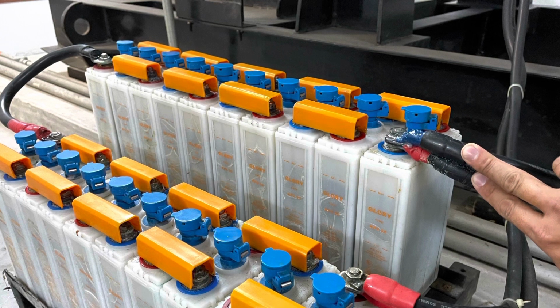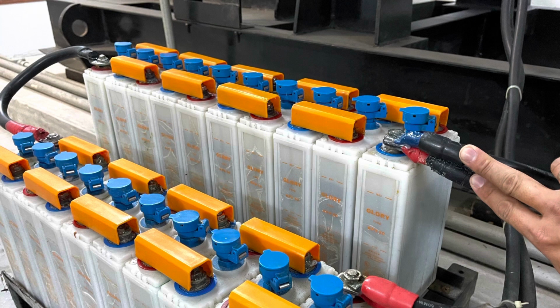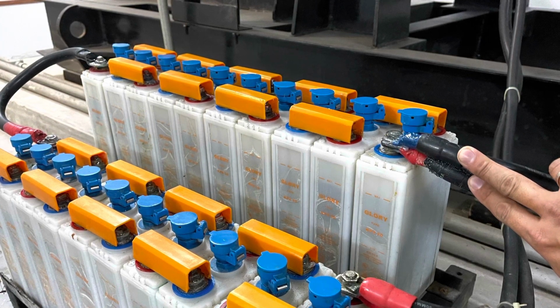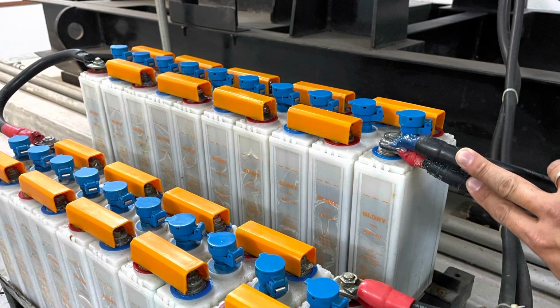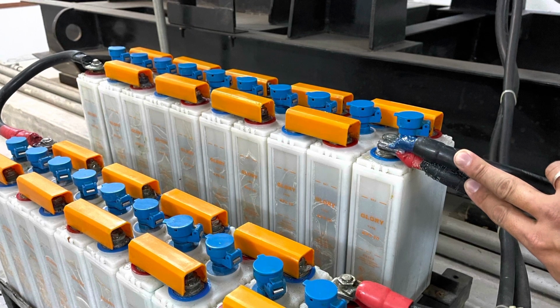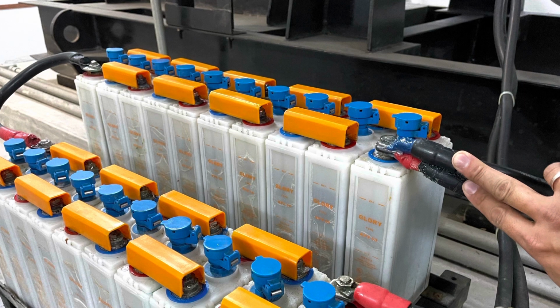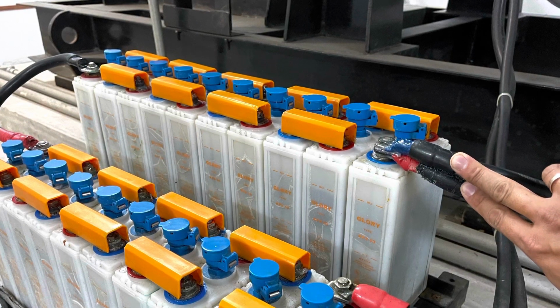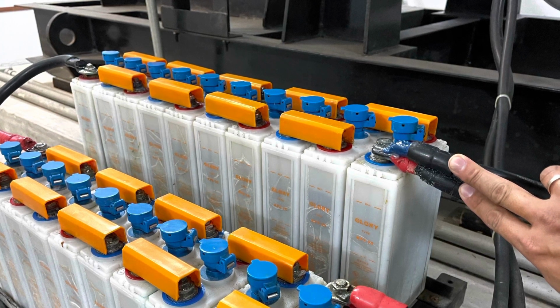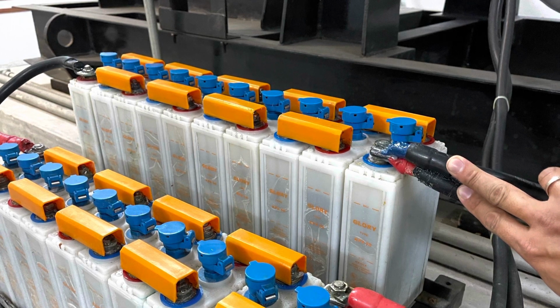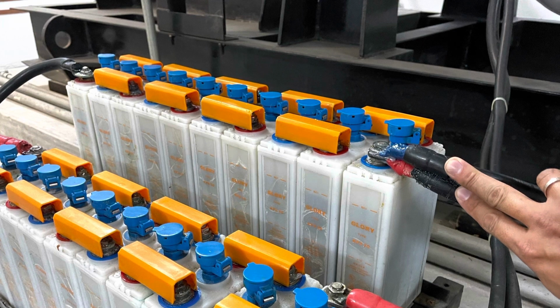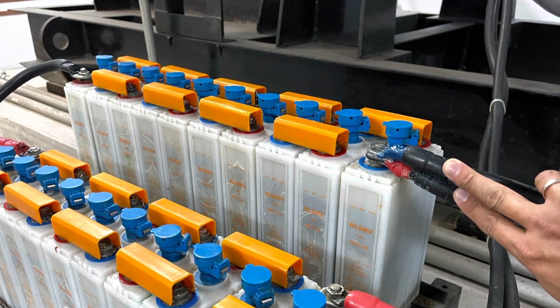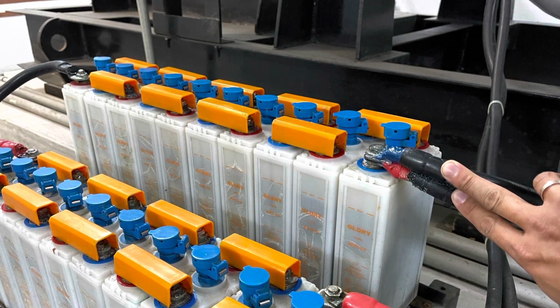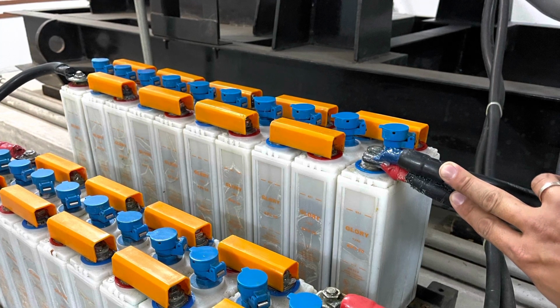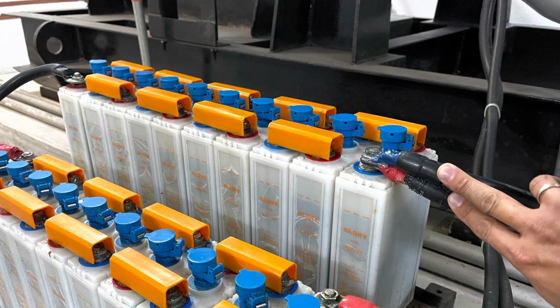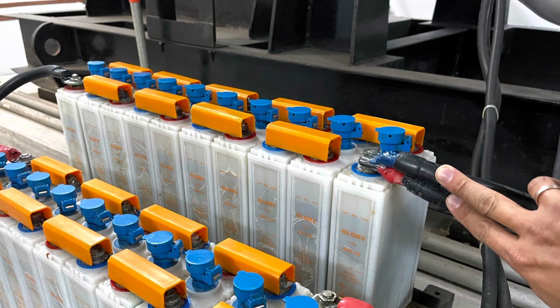From the video, you witness that after the genset has cranked and gone to maximum speed, the alternator starts providing 24 volt DC to charge up the battery, and then there's 240 volt AC available. If you activate the genset run relay, when this relay is activated, it will cut off the genset AMF panel battery charger. As you can witness, the light from the genset battery charger goes from on to off, because the genset battery is now charged by the alternator. So you have to cut off the genset panel battery charger. It cannot be both ways, otherwise the alternator will become a motor.